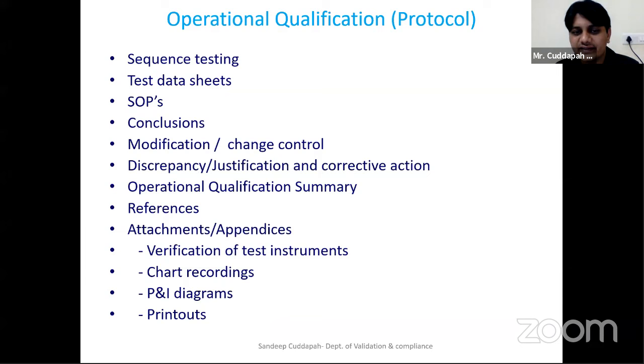Once your operational qualification testing is done, you will verify or implement the standard operating procedures. This is how you have to use this equipment. You will give certain steps, and based on that, the equipment will be used in future processes. In the same way, if anything is not meeting requirements, you will raise a change control and do the modification accordingly. As part of the attachments, you will attach the printouts from running the equipment, showing that the equipment is working and its basic requirements are met or not. You will attach those printouts to this operational qualification.